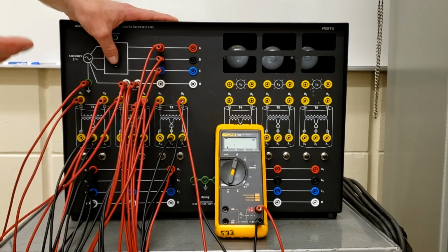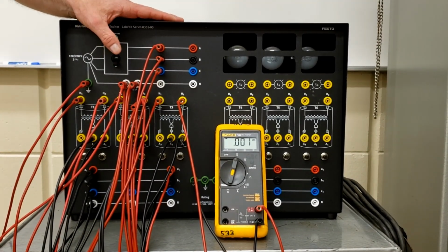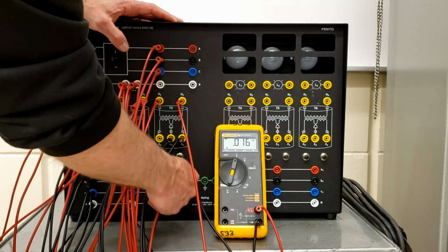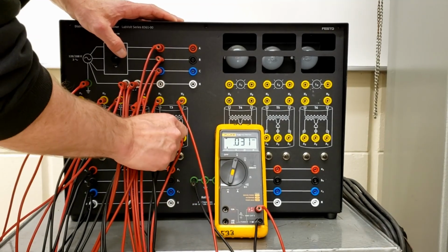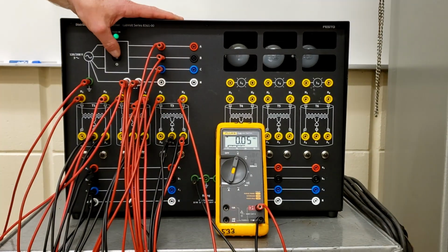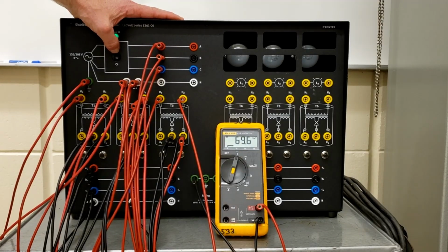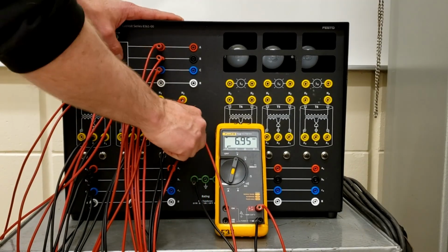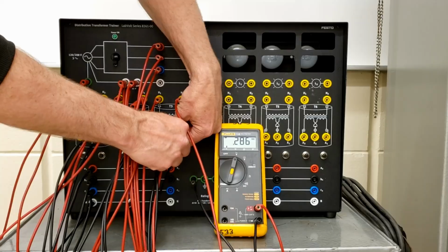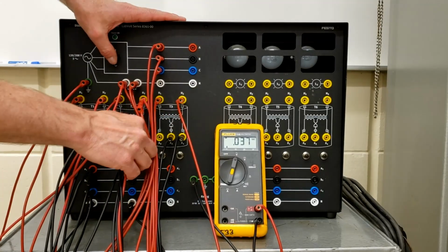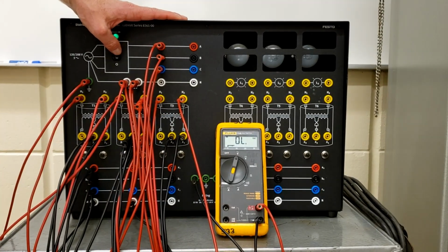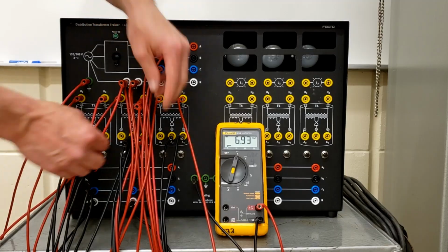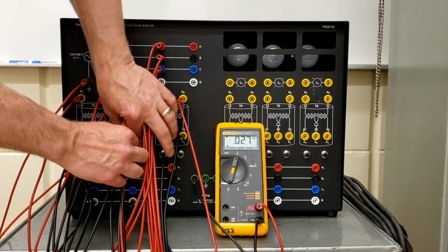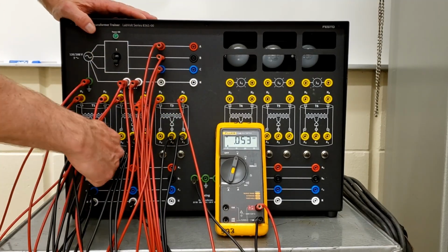Okay, if that's our line voltage, it's interesting they didn't ask for the phase voltage, but phase voltage between these should be 69 volts — 69 here on the C phase, 69 on the B phase. Beautiful, and the last meter measurement here should be 69 on the A phase.